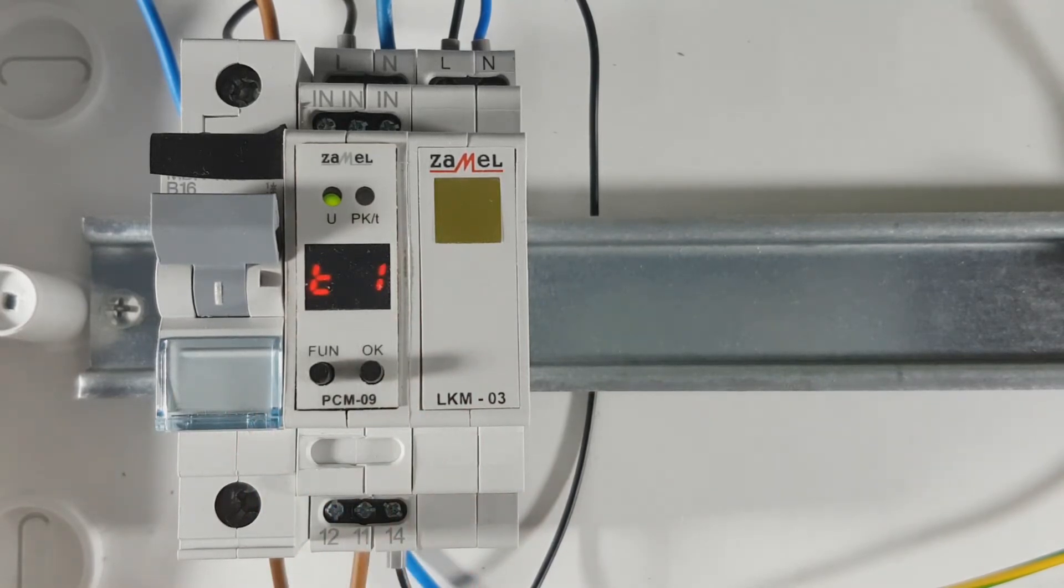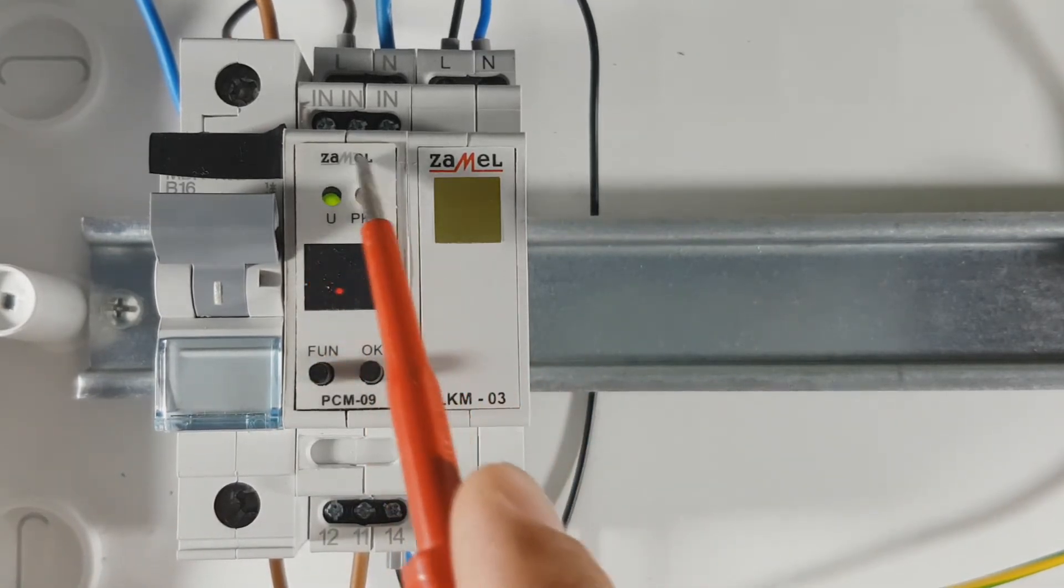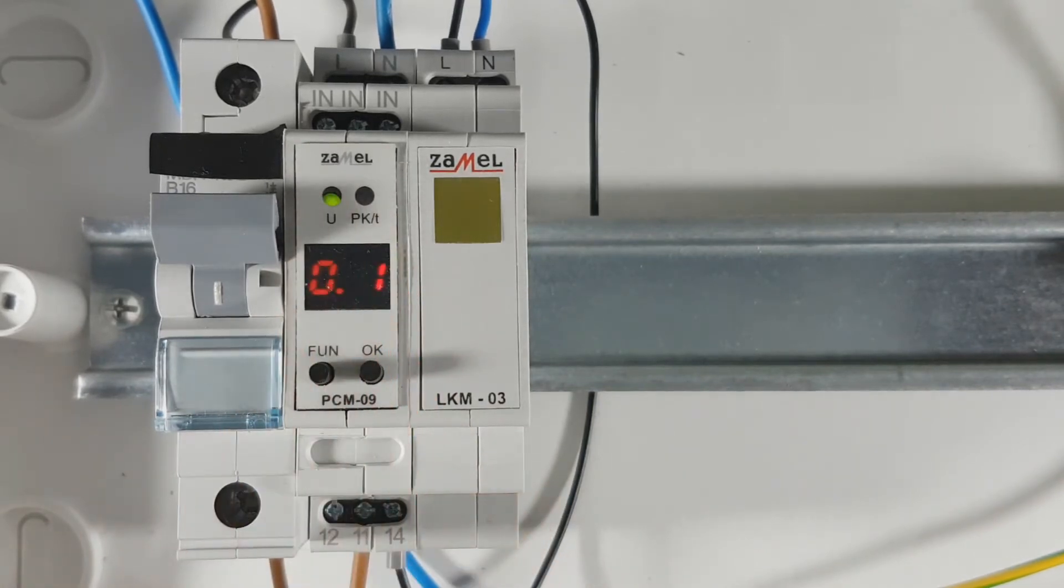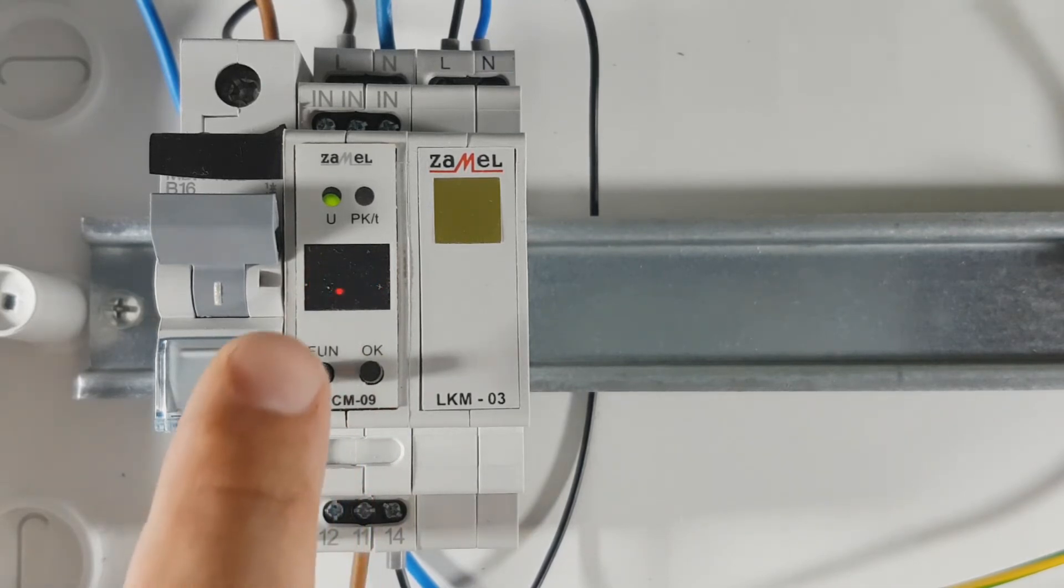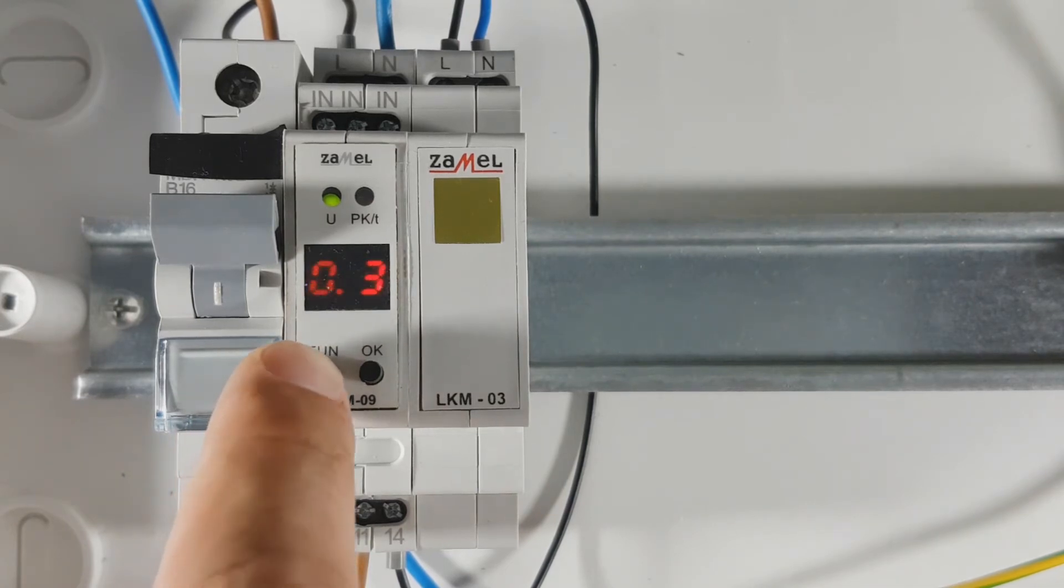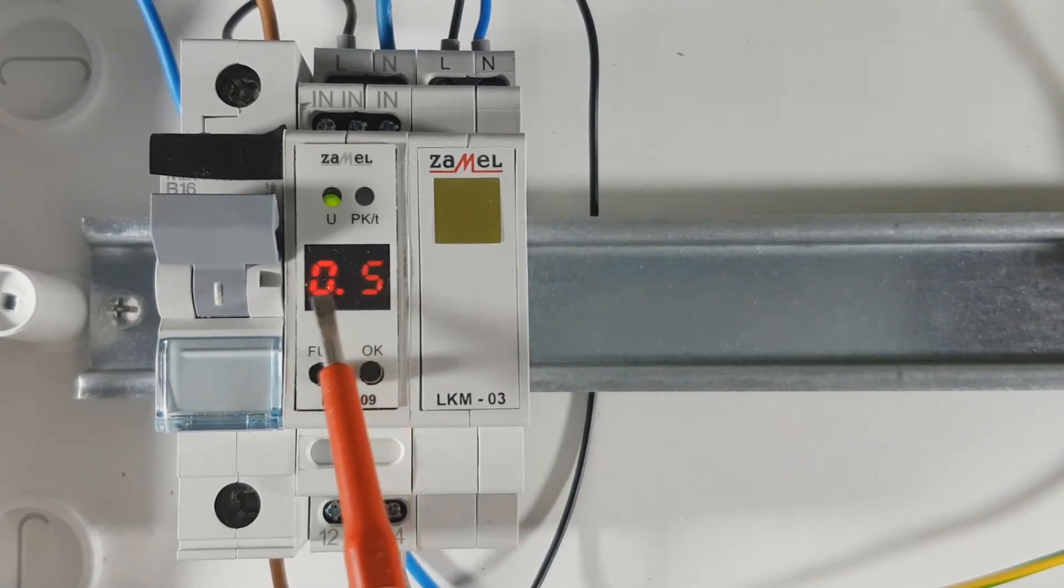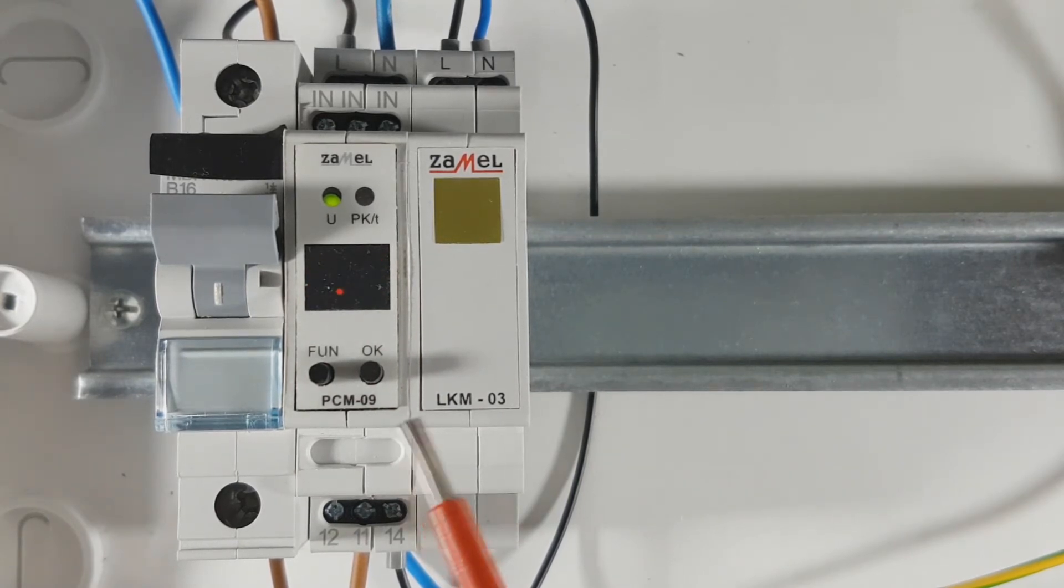Enter the menu by pressing the OK button. The PK LED indicates whether the time format will be in tenths of seconds, seconds, minutes, or hours. For example, setting the time T1 as half a second. For this purpose, increase the value indicated on the display by pressing the function button several times. The value appears on the display. Confirm it by pressing the OK button.